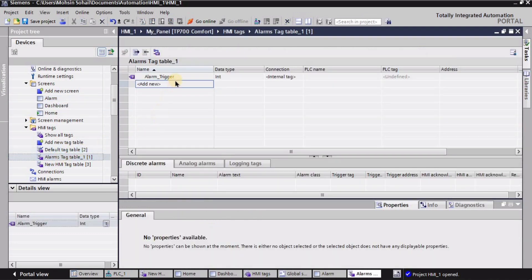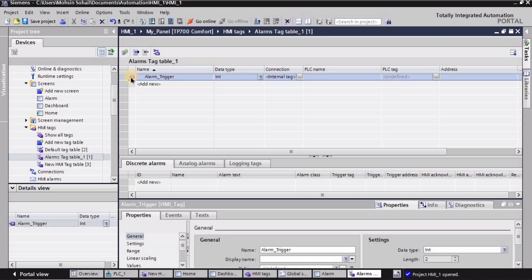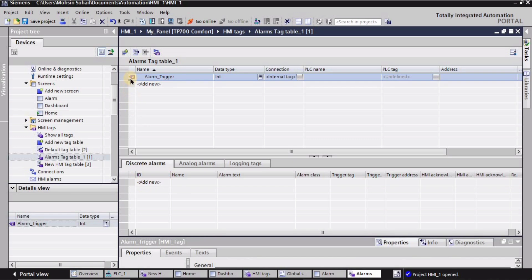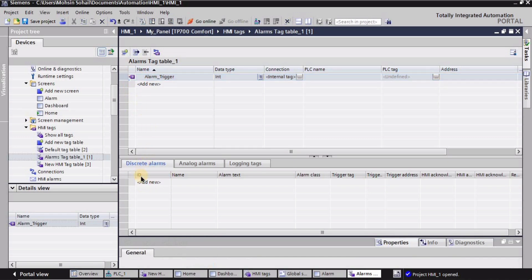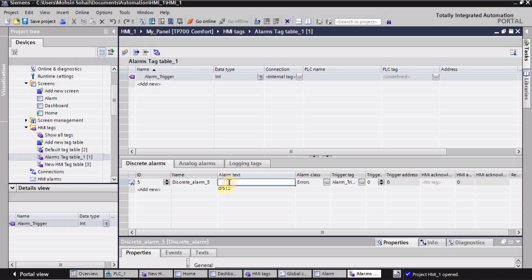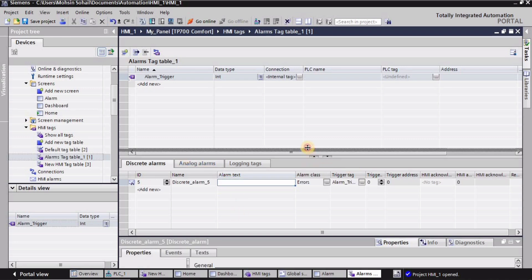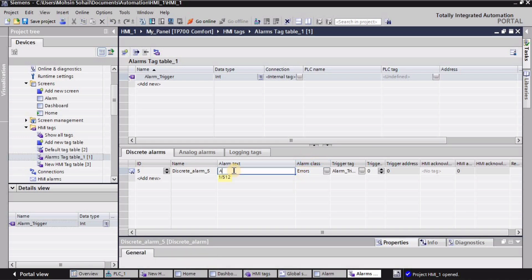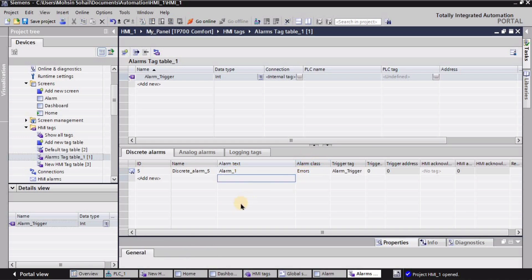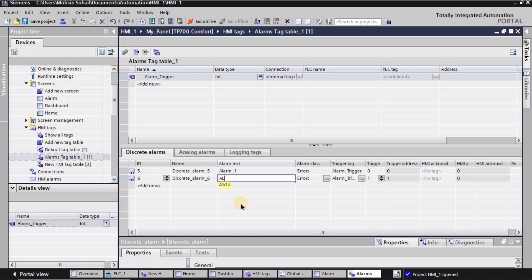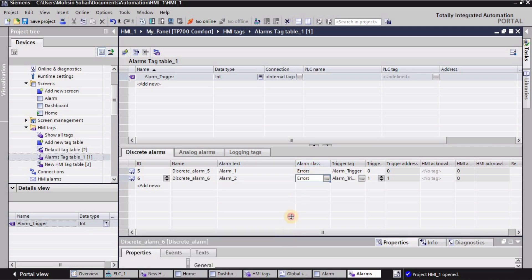After that I will go into the alarm tag table again. I'm going to select this whole entire row for the alarm trigger tag — make sure that you have selected this entire row — and then select 'discrete alarms'. In the alarm text column, I'm going to create two alarms and two warnings. I'm writing here 'alarm_one' and 'alarm_two' for the second. For the alarm class I will select 'error' for alarm_one and alarm_two.